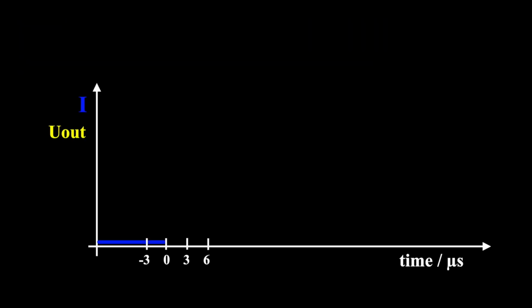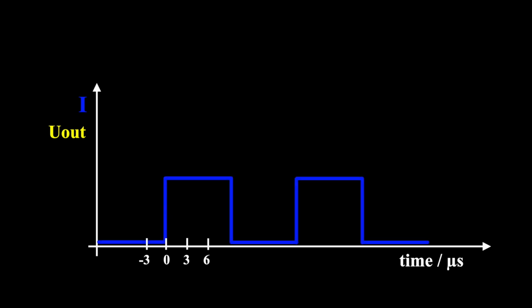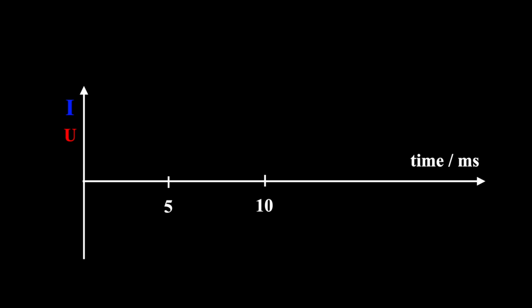The datasheet is just saying DC for direct current instead of telling us the bandwidth. Okay, let's estimate this from the so-called response time, which is less than 3 microseconds. That means if the measured current is jumping to a higher level, then the output signal is reaching its corresponding level 3 microseconds later. You could use the sensor for sampling an alternating current, as long as its period is greater than 6 microseconds. This is corresponding to a frequency of 166 kHz. Not bad, isn't it?